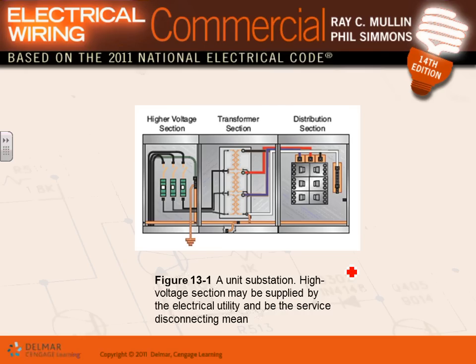Okay, so with the transformer comes something called a unit substation. Instead of having the transformer sitting outside, the utility asks you, as an owner, like a hospital, which is a typical application, or sport arenas, or a large industrial plant, to bring your 13,800 volt into this high voltage section. Look at the voltage. You disconnect and fuse it, then they are bussed internally into a transformer. This is all one big box.